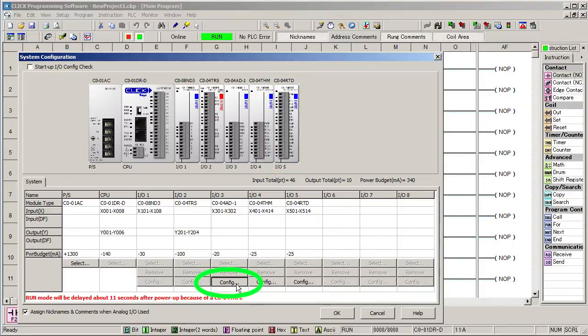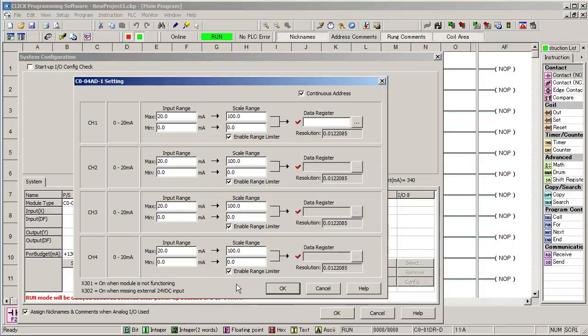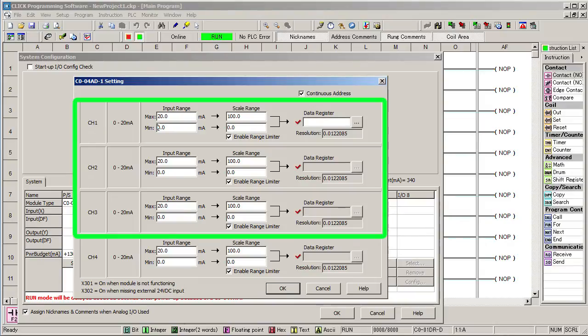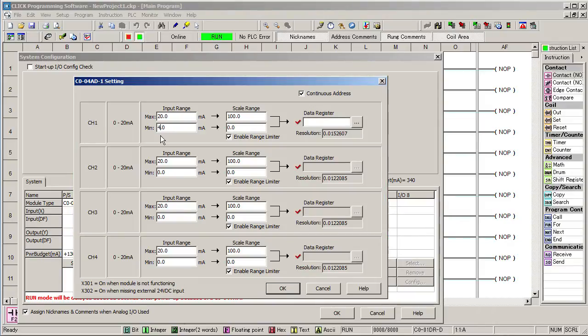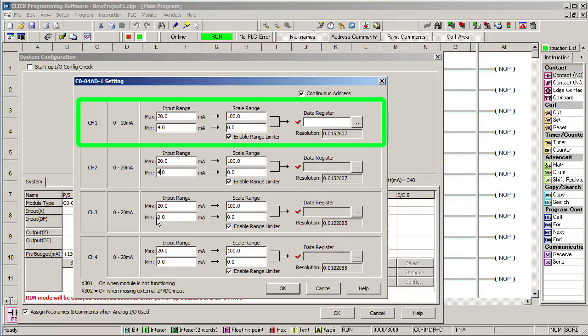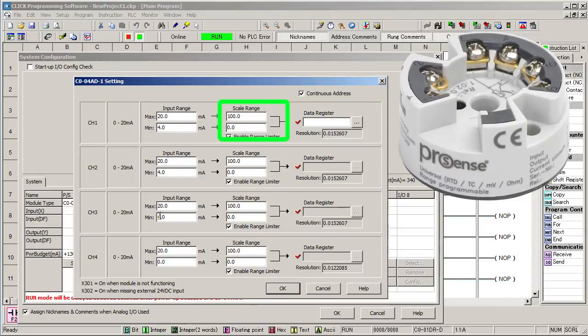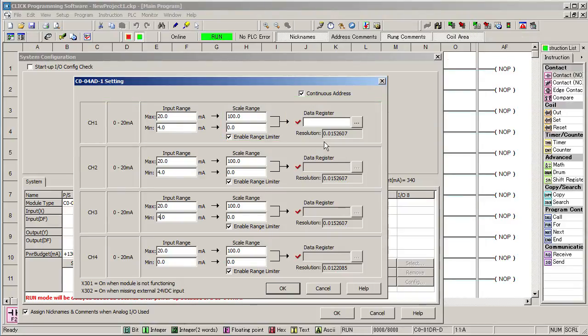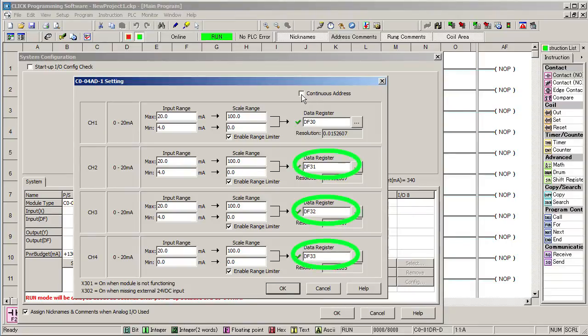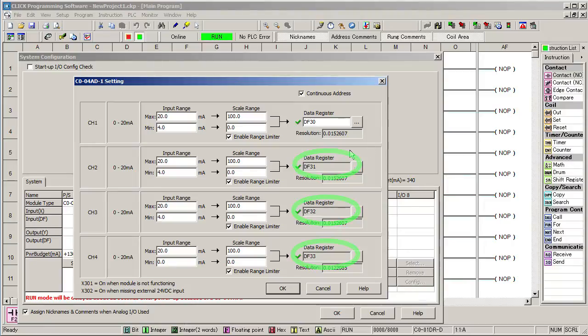To set up the analog module, we just hit configure. Our temperature transmitters are connected to these first three channels and are providing a 4 to 20 mA loop so we'll need to put 4's here. The first transmitter is a programmable sensor head transmitter that has been configured to give us 0 to 100 degrees F and we'll put that in memory location DF30. This check box up here says just fill in the rest of the registers for us. I really like that.